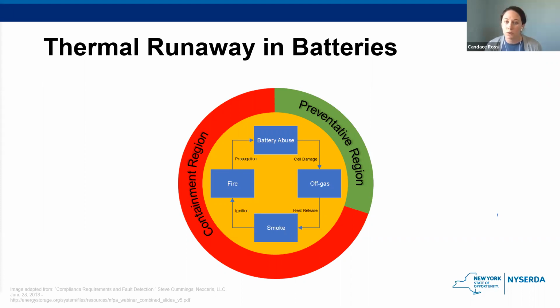There is also what we're referring to as the preventative region and the containment region based on how the risk has escalated. For example, if there is some sort of battery abuse, like a puncture or overheating of some sort that causes cell damage, the system may begin to off-gas. As that off-gas continues, it may begin a heat release, which would cause smoking. That could translate into ignition and a fire. So this is kind of a circular system or graph, where you can see how thermal runaway may occur in a battery. Like I said, the abuse can turn to off-gases, smoke, and fire, and that cycle may continue if there aren't the right containment and preventive measures in place.